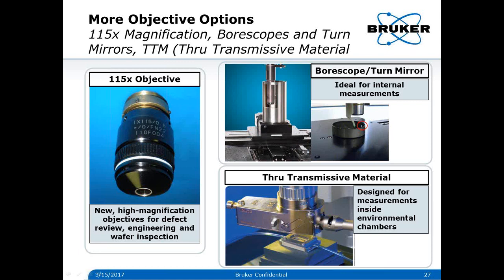On the upper right we have borescopes and turning mirrors. Borescopes are great for getting inside cylinder sleeves and measuring the surface roughness of the sides. We can mount a turning mirror — you can see the light circled in red bouncing off the side of a part — so now you don't have to turn the part vertically to measure inside; we turn the light bouncing off the side of the part to get a surface finish measurement. Below we have our TTM objective, or through-transmissive-material objective, initially developed for environmental chambers. There's a compensation glass in the objective so the signal coming off the part is the same optical path difference through the objective, allowing measurement into the environmental chamber.